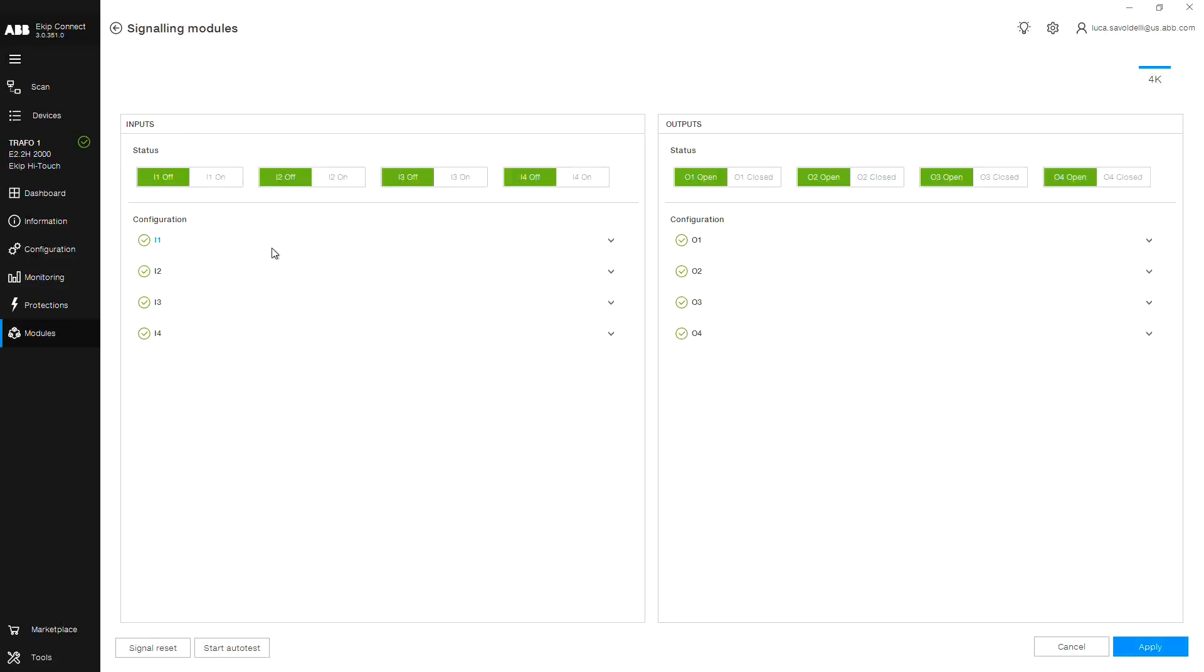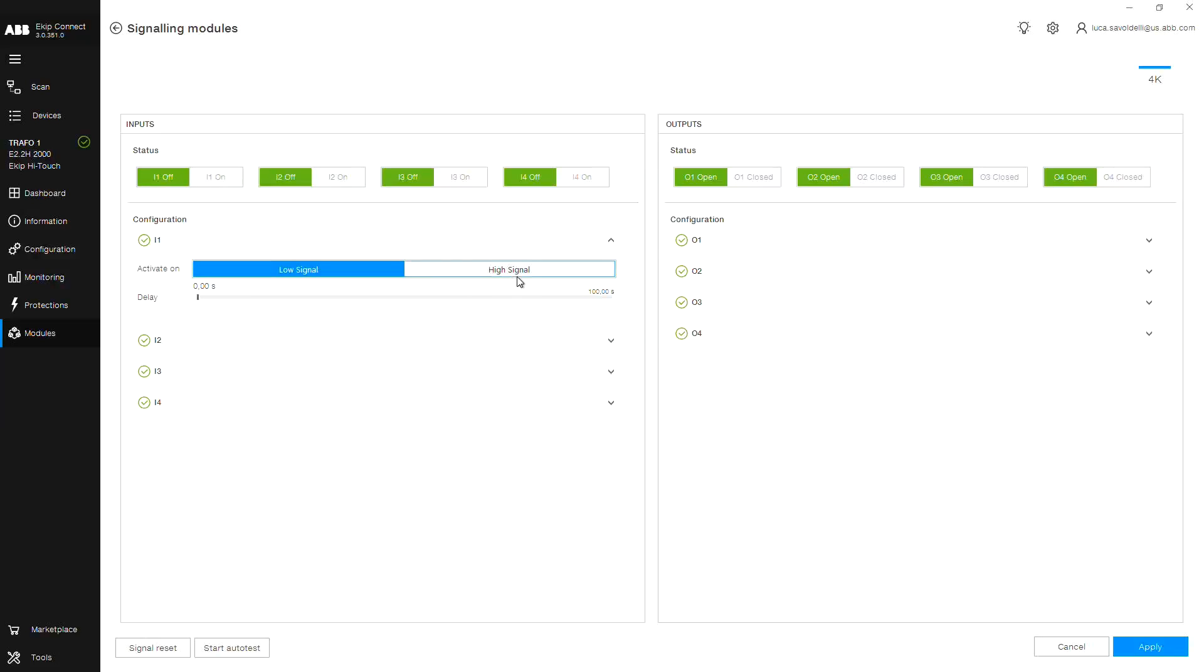Low signal or normally open, meaning the input is active when the contact is closed. High signal or normally closed, meaning the input is active when the contact is open, as well as a time delay. The signal must be open or closed for the length of the delay before the trip unit recognizes the input.